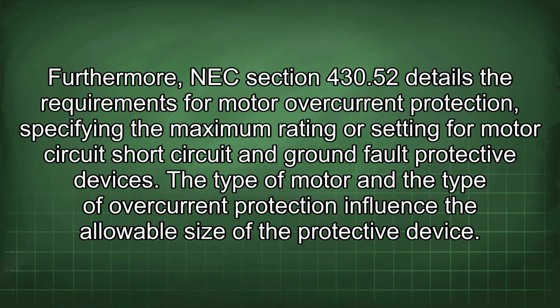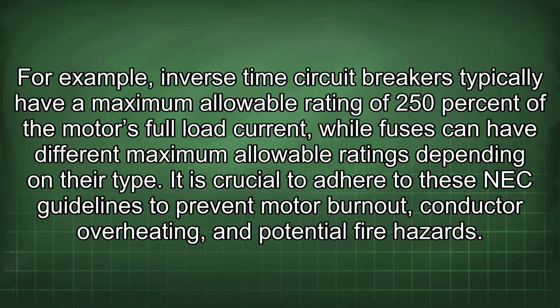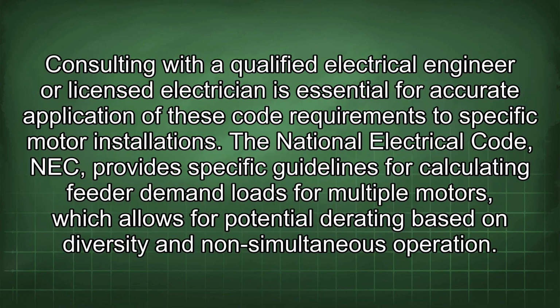Furthermore, NEC Section 430.52 details the requirements for motor overcurrent protection, specifying the maximum rating or setting for motor circuit short circuit and ground fault protective devices. The type of motor and the type of overcurrent protection influence the allowable size of the protective device. For example, inverse time circuit breakers typically have a maximum allowable rating of 250% of the motor's full load current, while fuses can have different maximum allowable ratings depending on their type. It is crucial to adhere to these NEC guidelines to prevent motor burnout, conductor overheating, and potential fire hazards. Consulting with a qualified electrical engineer or licensed electrician is essential for accurate application of these code requirements to specific motor installations.